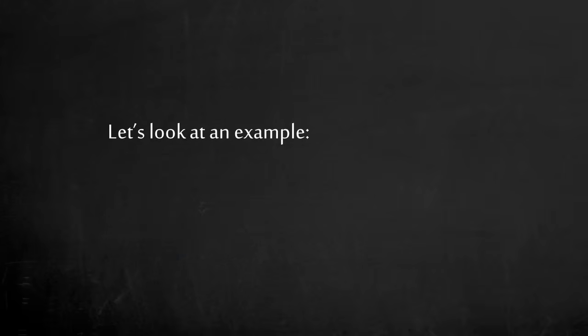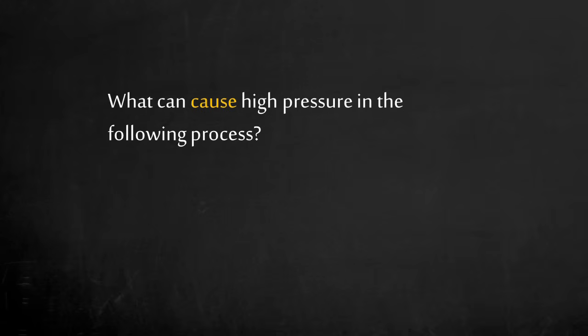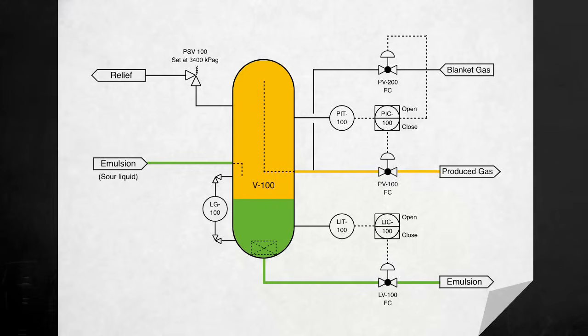Let's look at an example in the oil and gas industry. What can cause high pressure in the following process? Here you have a pressure vessel with product coming in as emulsion. This vessel has a pressure control loop and a level control loop. This vessel has a maximum allowable working pressure slightly above the pressure safety valve set point of 3400 kPaG. Let's start off with the high pressure deviation from normal operation. Can you think of a cause?